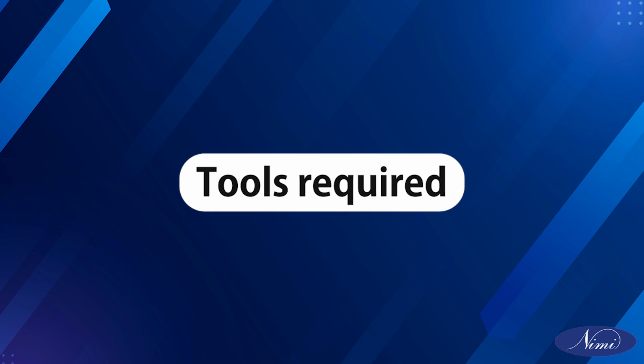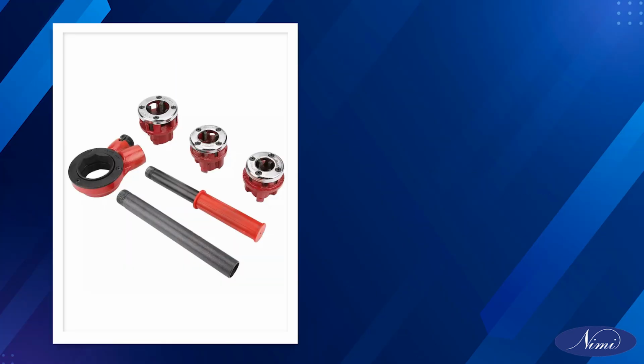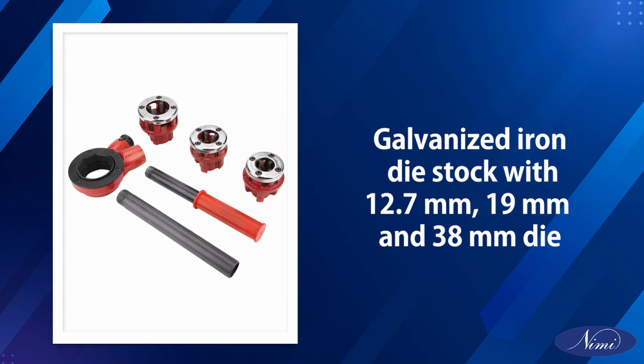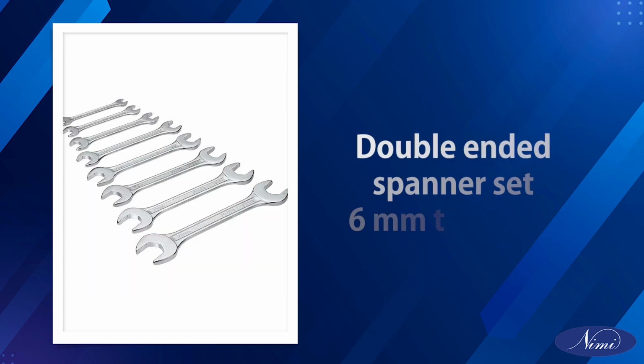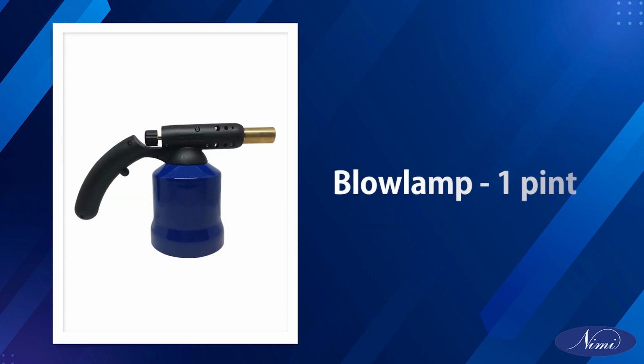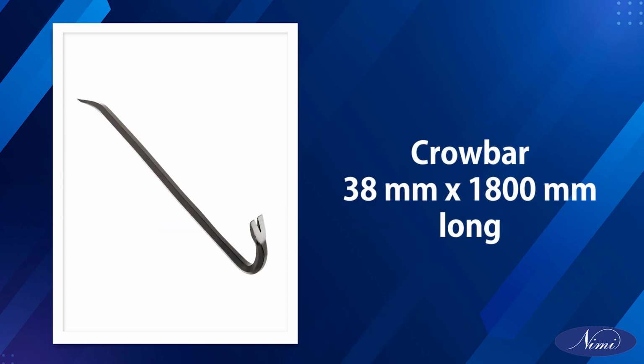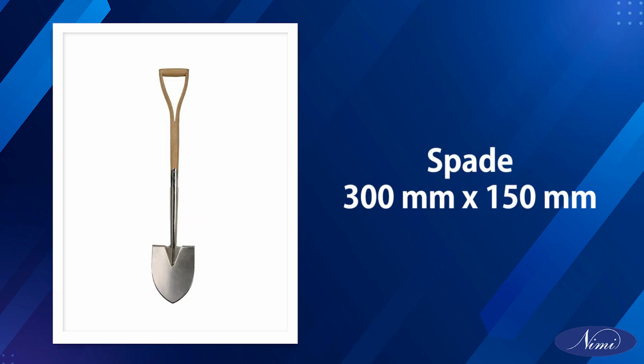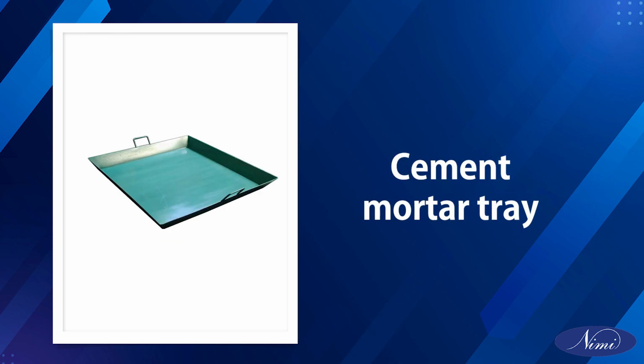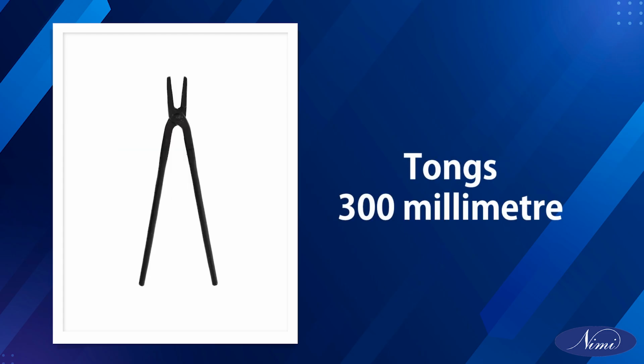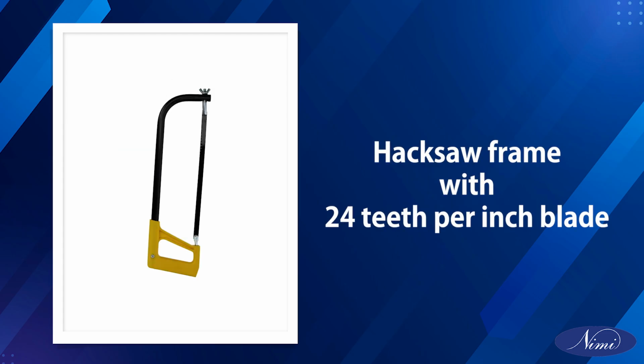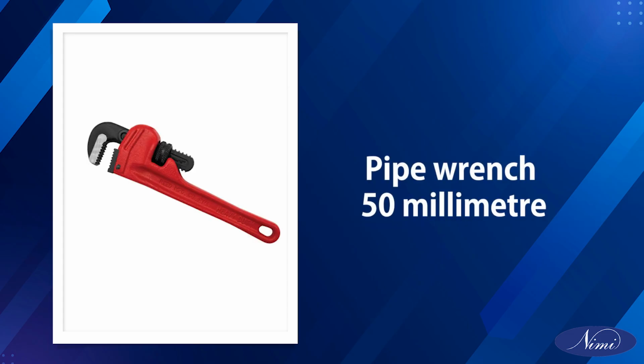Tools required. Earth tester. Galvanized iron die stock with 12.7 mm, 19 mm, and 38 mm die. Double-ended spanner set 6 mm to 25 mm. Blow lamp 1 number. Crowbar 38 mm into 1800 mm long. Spade 300 mm into 150 mm. Cement mortar tray. Tongs 300 mm. Hacksaw frame with 24 teeth per inch blade. Pipe wrench 50 mm.